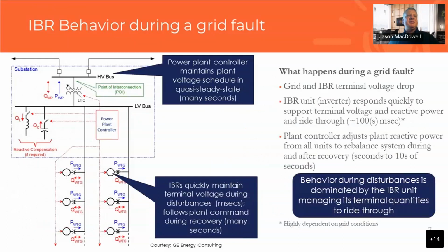I think that's certainly something that, in the steady state or quasi-steady state, we want to do. And that certainly holds true before a disturbance and after a disturbance. During a disturbance, however, the terminal voltage of the plant, and particularly of the inverter-based resources, is managed by the inverter-based resource controls itself. So during the voltage depression, during the fault event, the inverters will do what they need to do to inject reactive current.